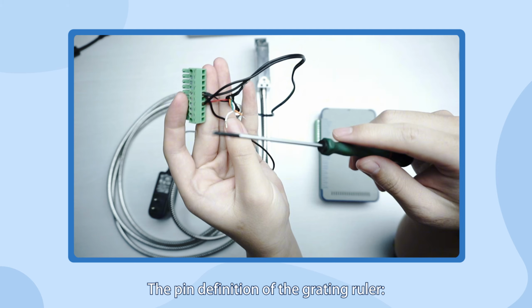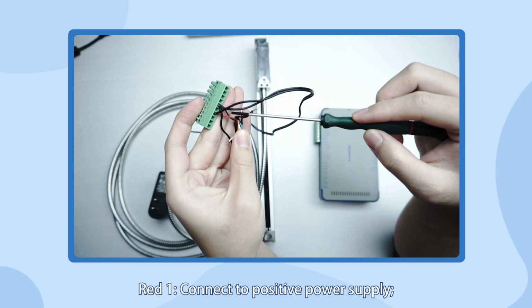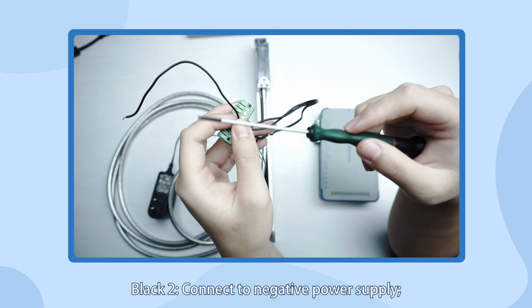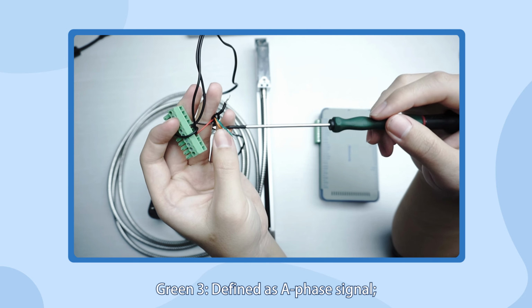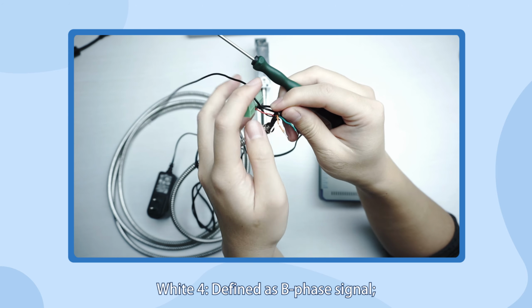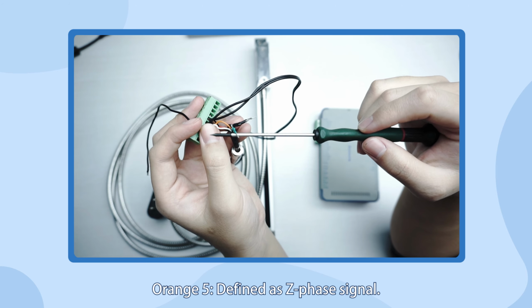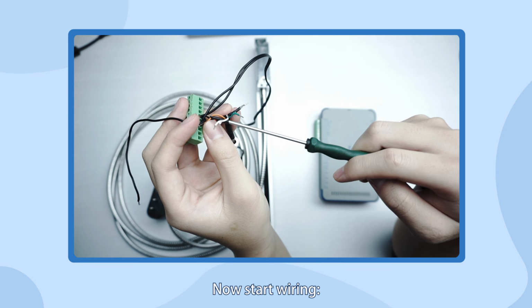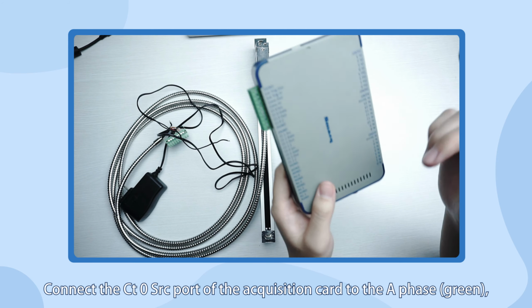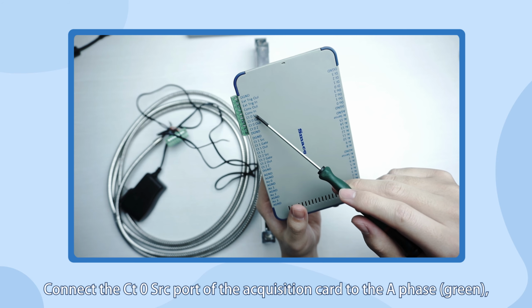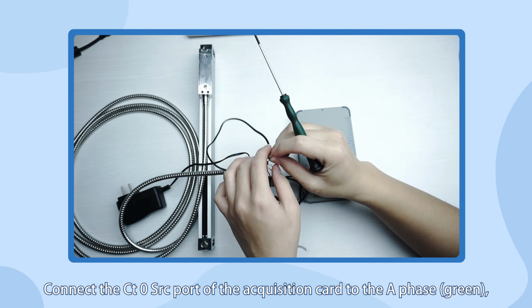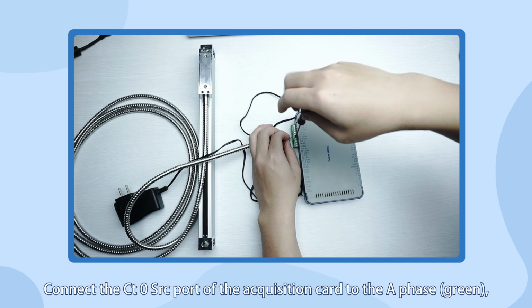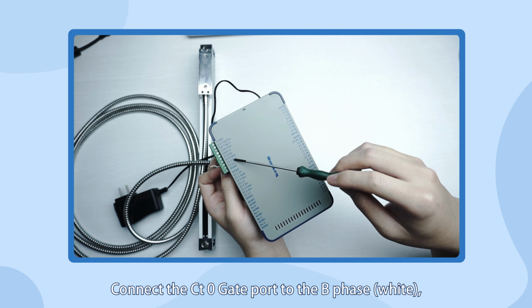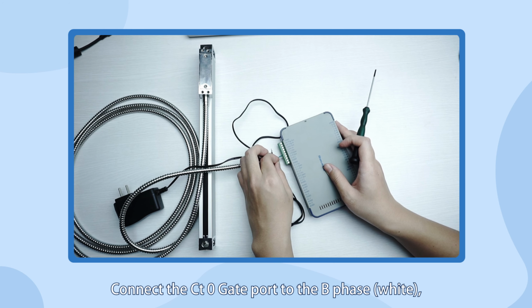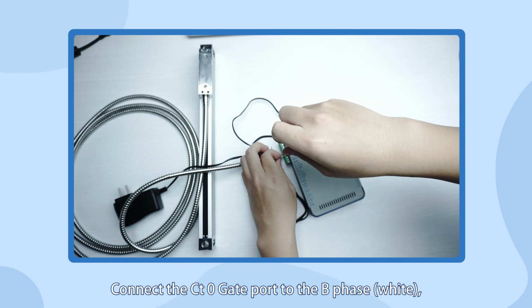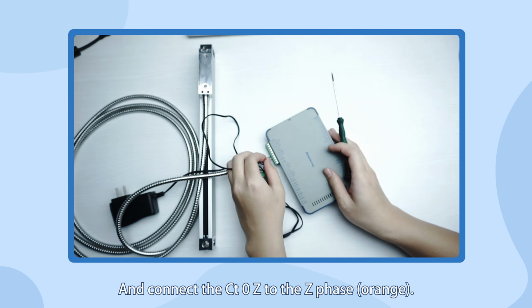The pin definition of the grating ruler: red 1, connect to positive power supply; black 2, connect to negative power supply; green 3, defined as A phase signal; white 4, defined as B phase signal; orange 5, defined as Z phase signal. Now start wiring. Connect the CT0 SRC port of the acquisition card to the A phase. Connect the CT0 gate port to the B phase. And connect the CT0Z to the Z phase.